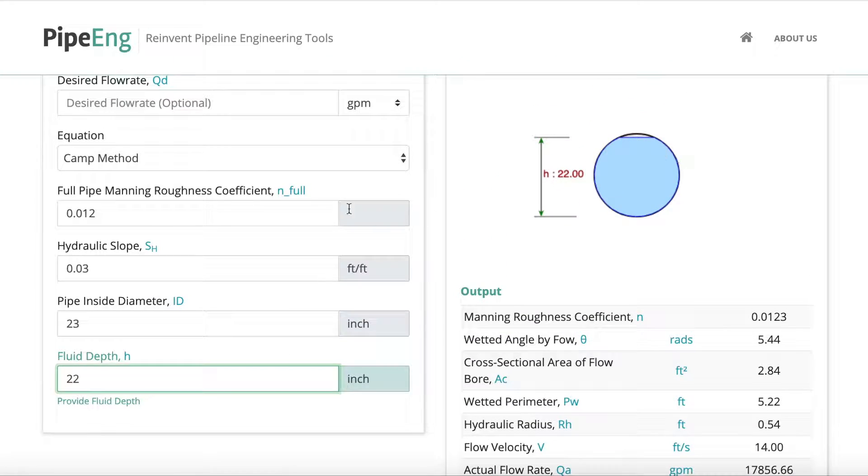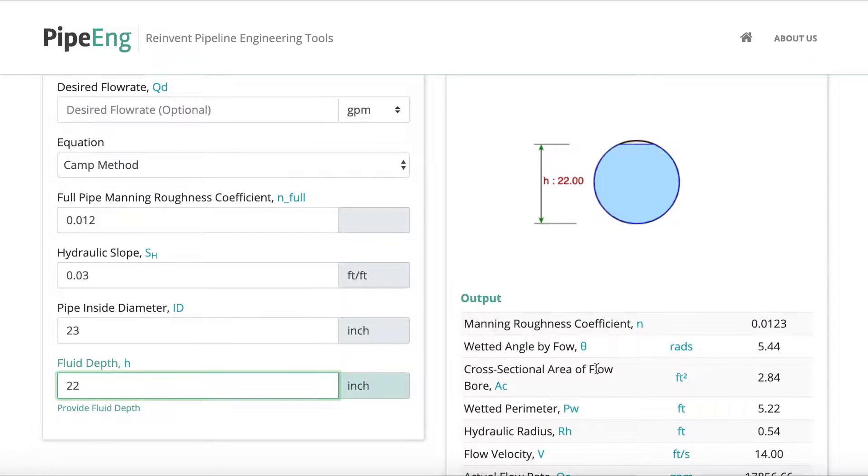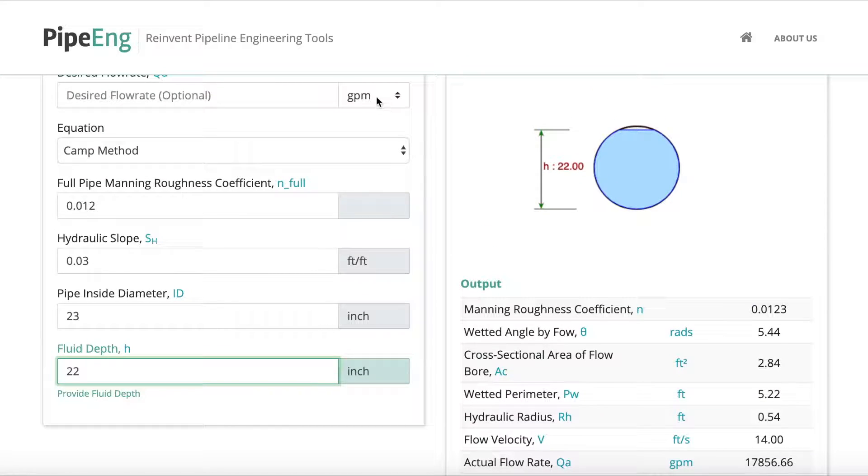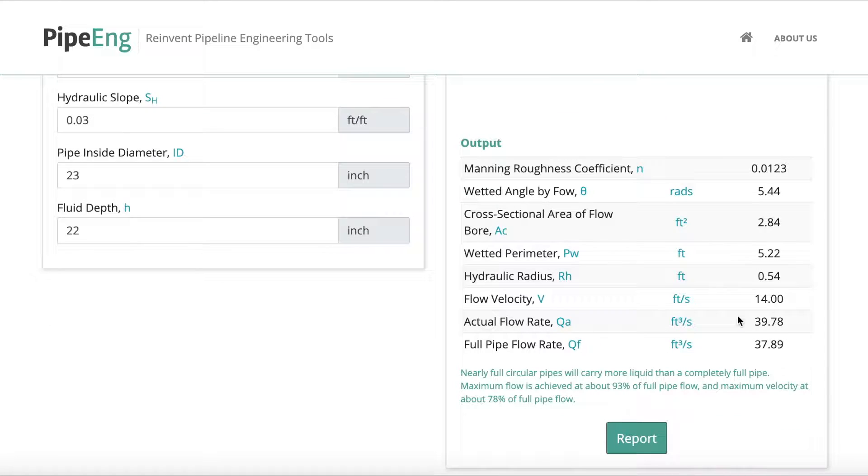But anyhow, so this is how you can use the slope available and the size to get an idea of what's going to be the flow rate to make sure this can handle your design conditions. And we just want to point out that right now it's showing as gallons per minute. If you want to change the units to cubic feet per second, which is also pretty common for open channel pipeline, you can just change it here. So that will help you to change the units.